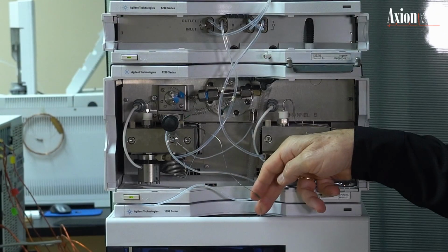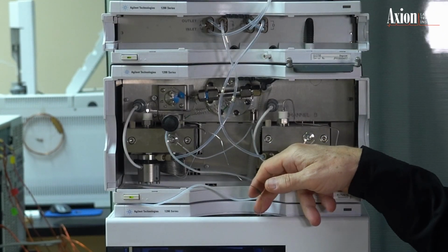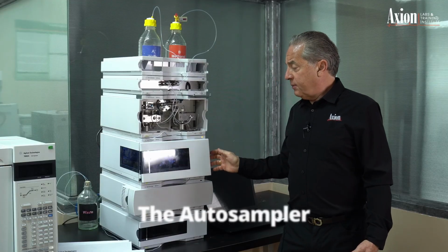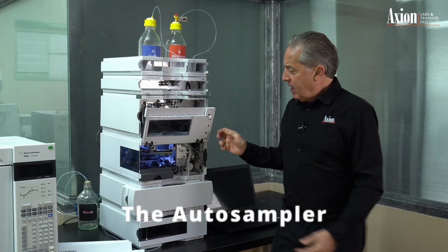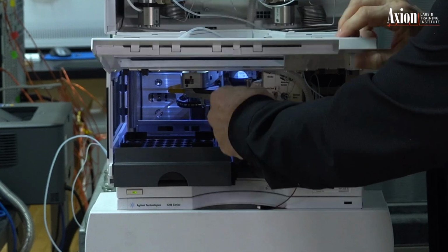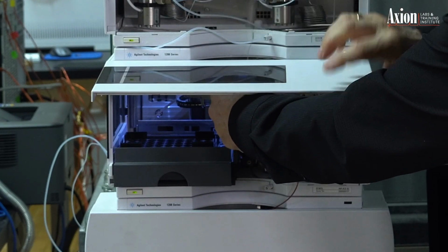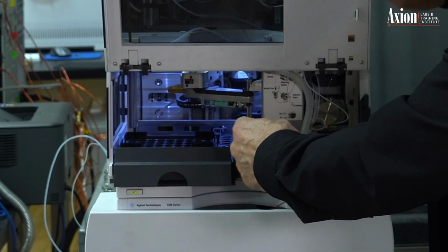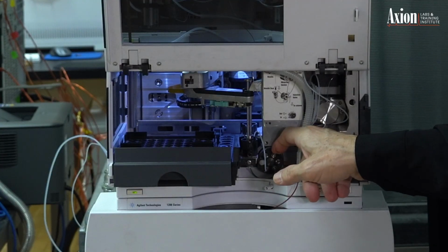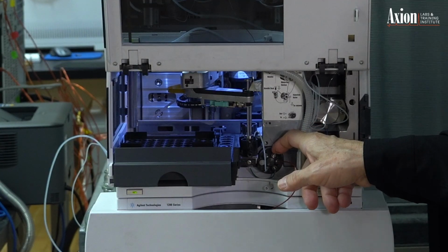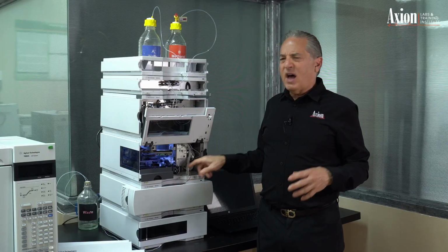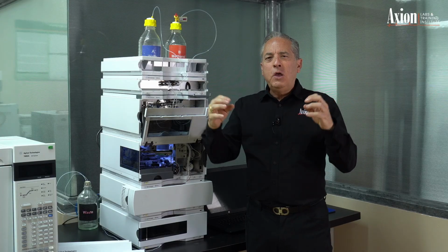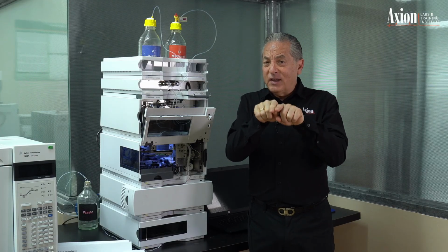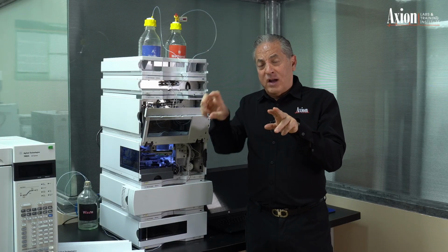So now my mobile phase, the next step is to pick up the sample. So we're gonna go down to the autosampler. I'll pop this guy open, and this is the tubing. I don't know if you can see. Here's coming from the pump. It's going to the autosampler, and the autosampler, its job is just to insert the sample. So imagine we have this high pressure flow going through this piece of tubing. We would like to just insert our sample into that and allow it to transfer to the column.